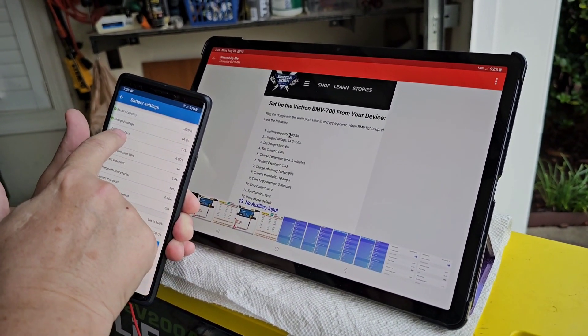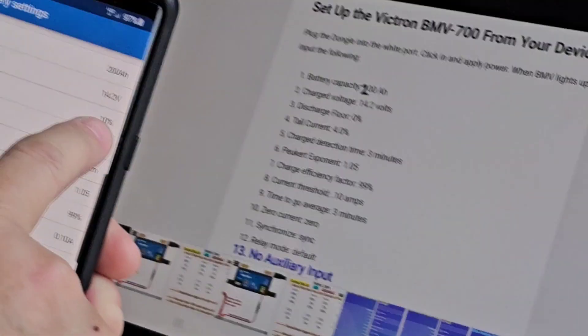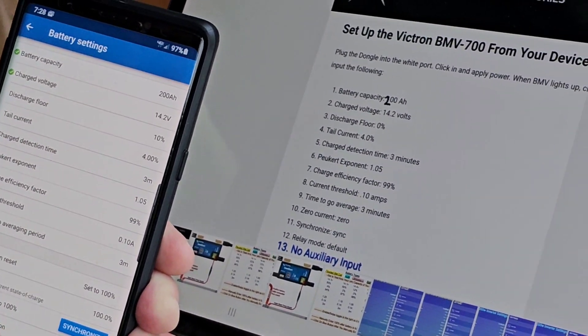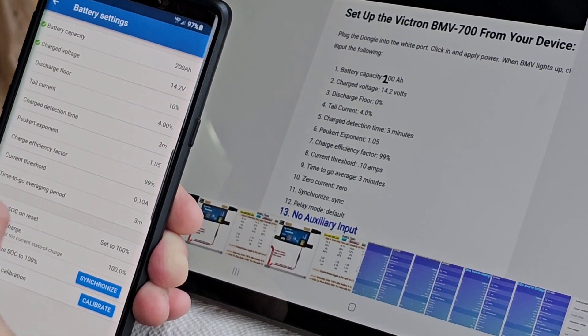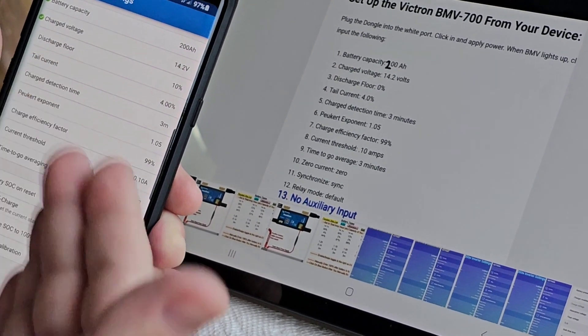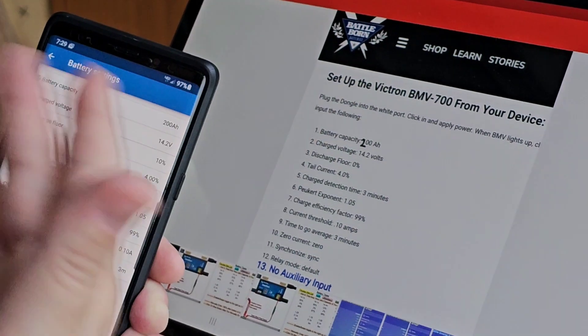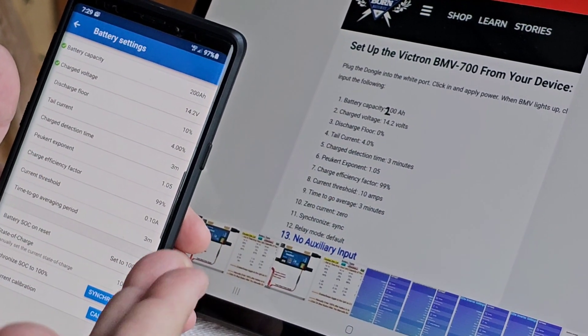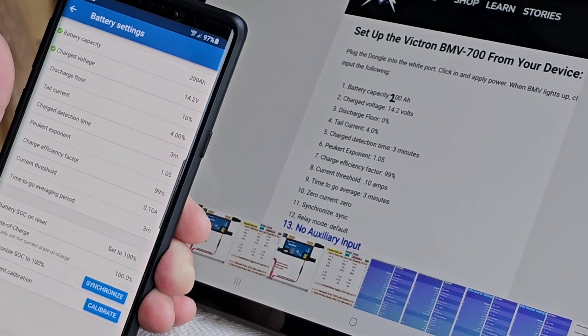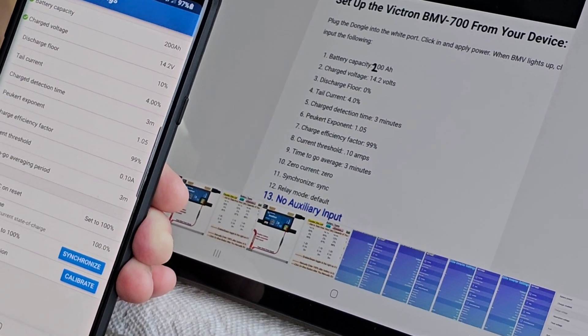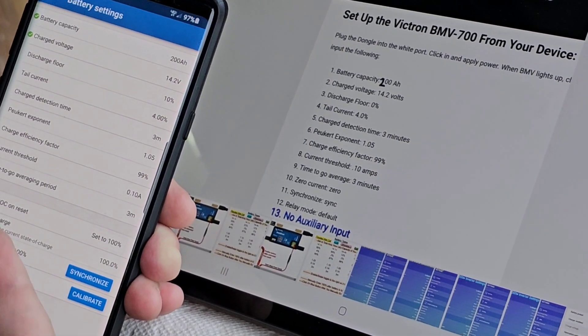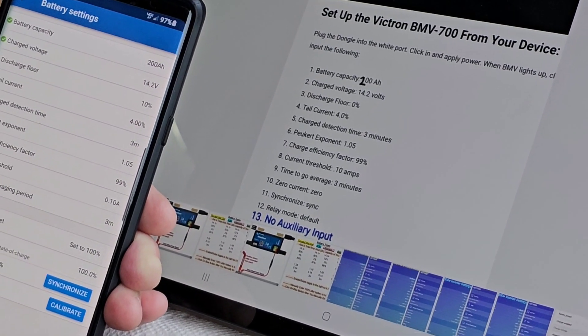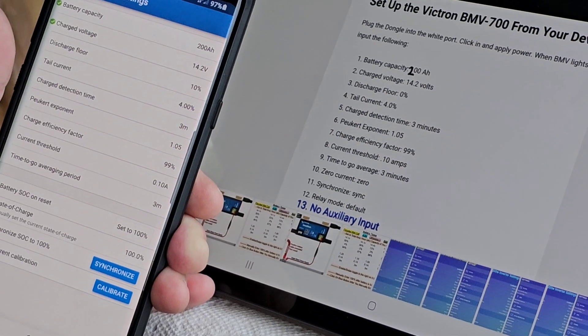And I put the discharge floor at 10% because what that means is it's going to tell you how much time you have remaining when you're monitoring for the battery to get down to 10% or you've used up 90%. I don't like to go to zero. I don't like to use any battery, lithium battery for sure, to zero. I like to give myself some margin. So I set the discharge floor to 10%. So I have a last 10% once I've used it up the way that I do when I'm monitoring.